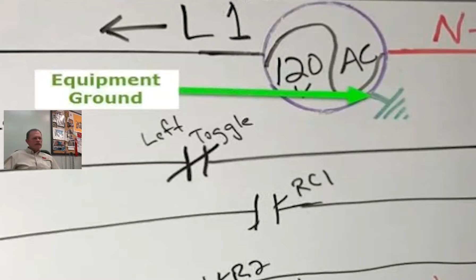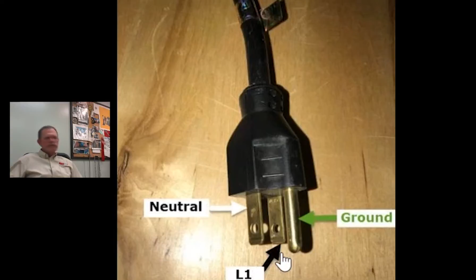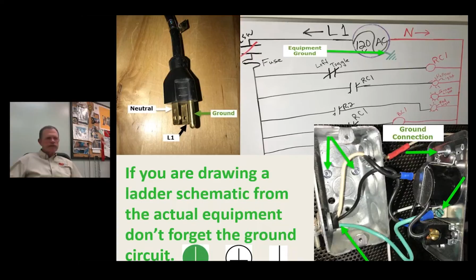So just to connect the dots, here's a 110 volt plug. You've got neutral, L1, and the ground leg for the 3-prong plug. You've got the ground connection at the wiring box where the switch was. Here's my ground wire coming in, it ties to the metal cover of the switch box. The metal cover is screwed to the metal box, and the metal box is screwed to the wiring board frame, so the entire thing is grounded, which is a good thing for you guys, the technicians, and your customers. You definitely want to have ground.